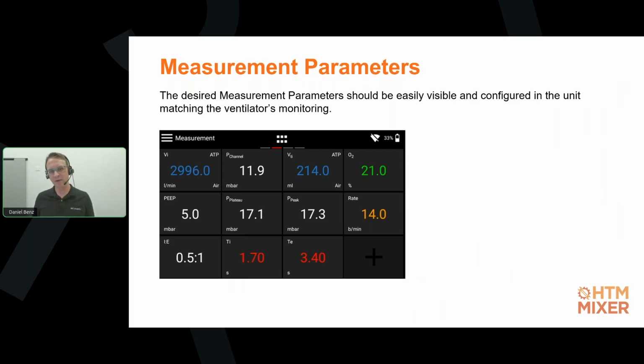So it's important that we understand which value we need to look at, so that we know what terminology our gas flow analyzer and our ventilator are using, so that we can set up the right value on the monitoring view of our gas flow analyzer and also have it set up in the right unit of measurement. Otherwise we probably compare different units or different parameters, and we can have different readings.